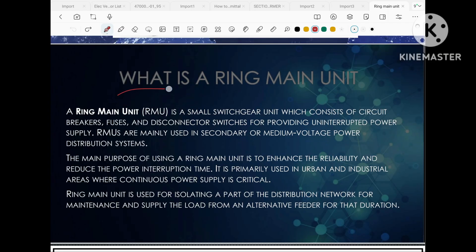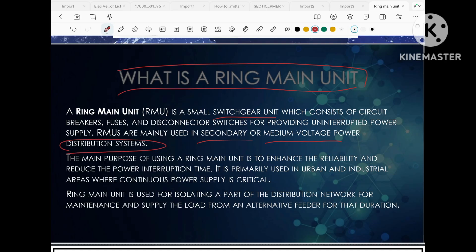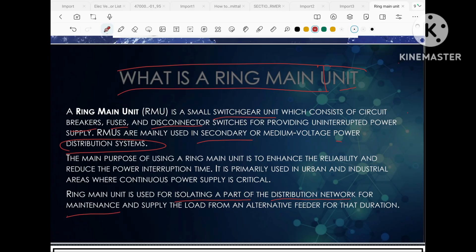The first question arises: what is ring main unit? Ring main unit is a switchgear unit which is generally in the secondary or medium voltage power distribution site. This consists of circuit breakers, fuses, and disconnectors. The main purpose of ring main unit is to enhance the reliability of the power and reduce the power interruption time. Ring main unit is used for isolating the faulty part of the distribution network in order to do maintenance, but at the same time it will supply the power to the load by using an alternative feeder for that duration.